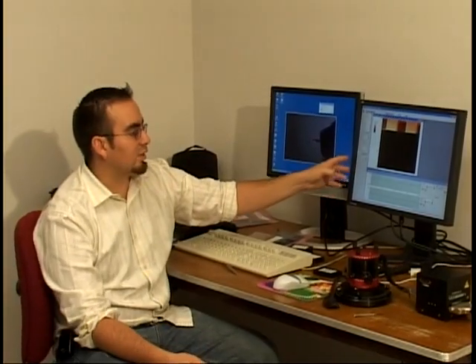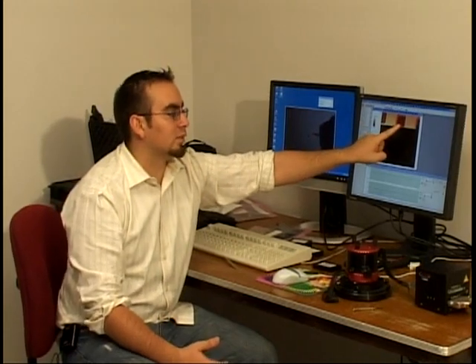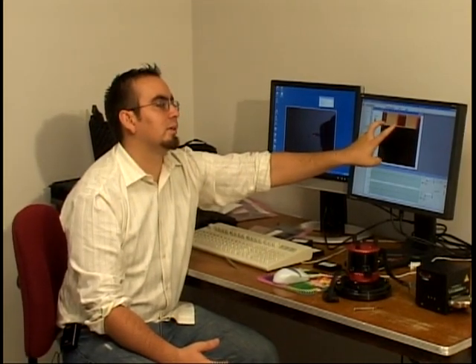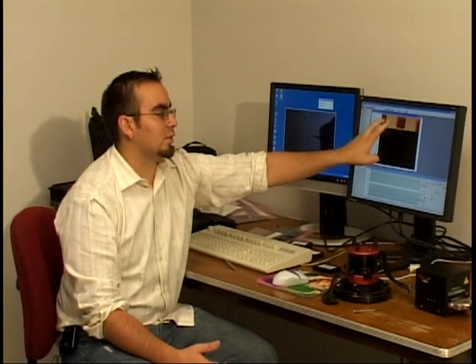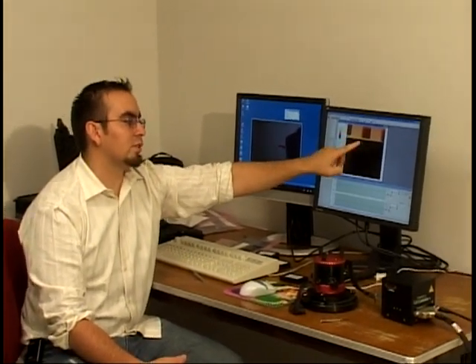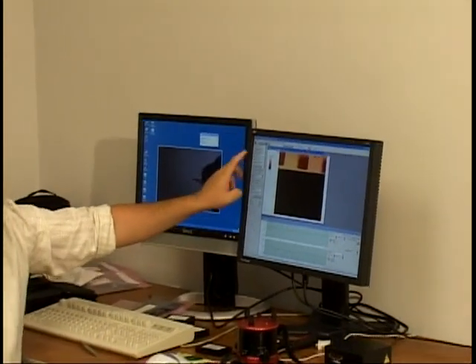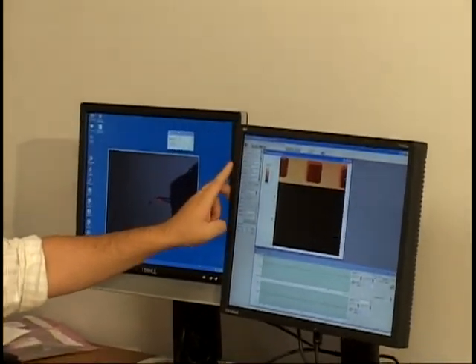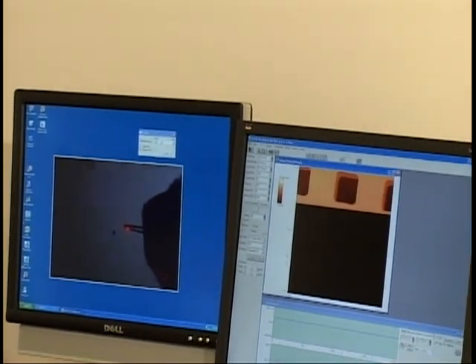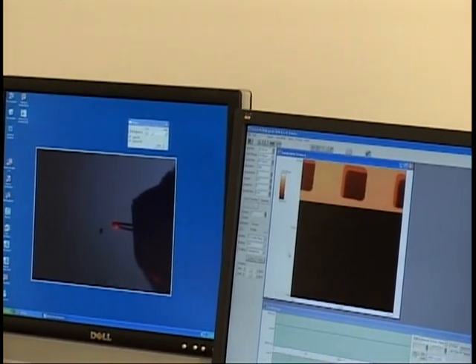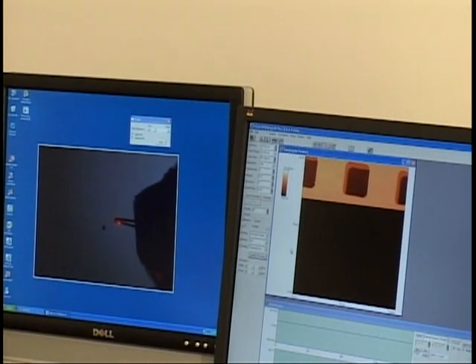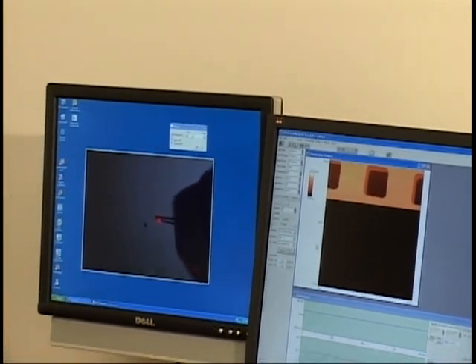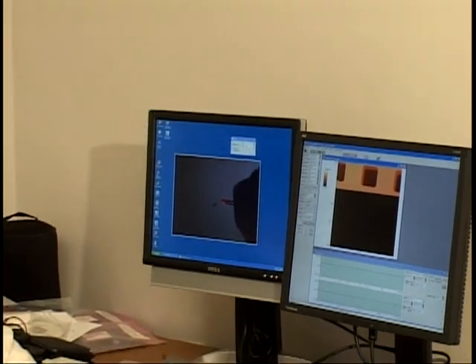In this image, you'll see the 20 micron scan size. Right now, we're looking at a 10 micron grating, XY calibration grating. So each pit's about 5 microns, and the space between it is about another 5 microns. So you'll see from one end of the pit to the other should be about 10 microns. We're doing it at 20 micron scan size at 60 microns per second with a resolution of 300 points. So 300 is 300 points in each line. And that resolution could go up to 1,000 points per line.